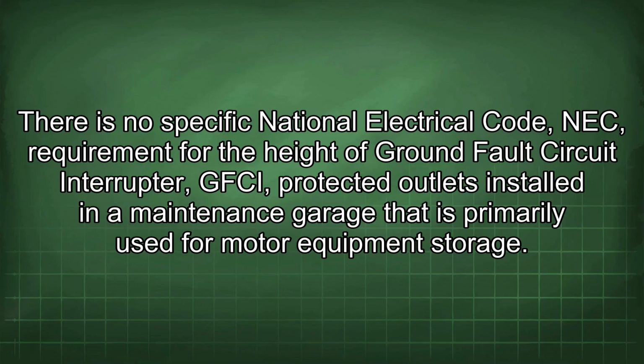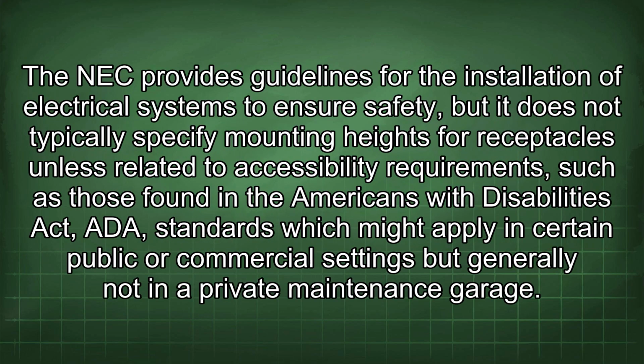There is no specific National Electrical Code (NEC) requirement for the height of ground fault circuit interrupter (GFCI) protected outlets installed in a maintenance garage that is primarily used for motor equipment storage. The NEC provides guidelines for the installation of electrical systems to ensure safety, but it does not typically specify mounting heights for receptacles unless related to accessibility requirements such as those found in the Americans with Disabilities Act (ADA) standards, which might apply in certain public or commercial settings but generally not in a private maintenance garage.